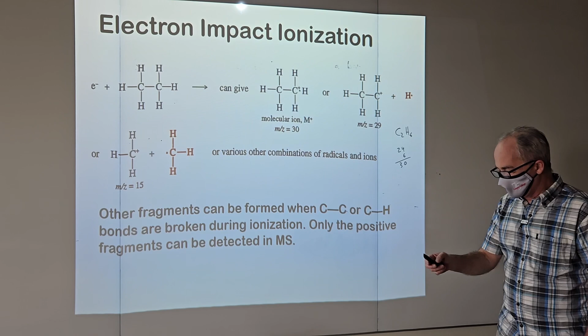So you put some sample on this probe and you put it into this high vacuum situation. There's something that makes an electron beam. The electron beam hits the sample, you make those molecular ions. There might be some accelerating plates. Potential difference imparts kinetic energy to the molecular ion, and this thing flies down through this magnet. And then all those rules of physics take over, and some ions are kind of heavy and they just slam into the outside of the instrument. Some are too light and they bend too much and slam into the inside of the instrument. But the ones that are just right come through and they go through a detector, and you get a blip whenever that happens, a count.